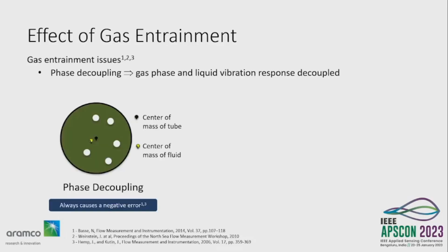The first error is due to what we call phase decoupling. The center of mass of the tube and the center of mass of the liquid are different, meaning the gas isn't following the liquid in vibrating along with the tube. It's physically decoupled, and this always causes a negative error, meaning you're always underestimating how much fluid is within the tube.